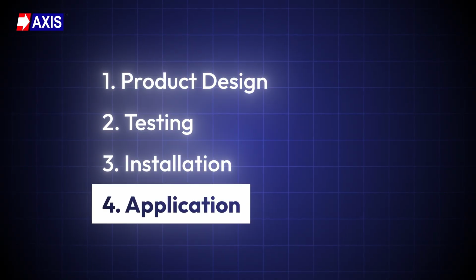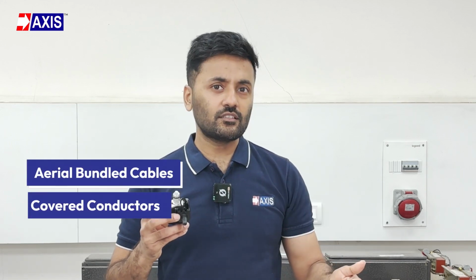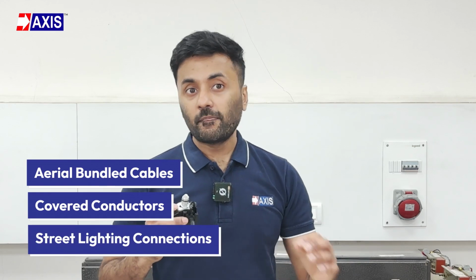Last thing, the application. IPCs are designed for overhead distribution networks such as aerial bundled cables, covered conductors, and street lighting connections. They are not intended for indoor wiring or meter connections. In such applications, tightening the IPC would apply rotational and pulling forces on the conductor, which will disturb existing terminations and the meter or distribution board. This will lead to loose connections, overheating, and long-term reliability issues.